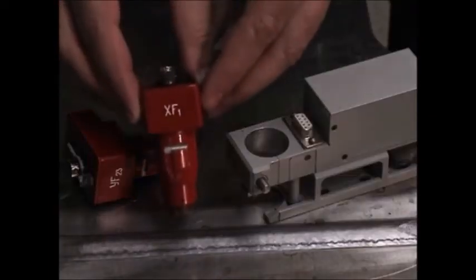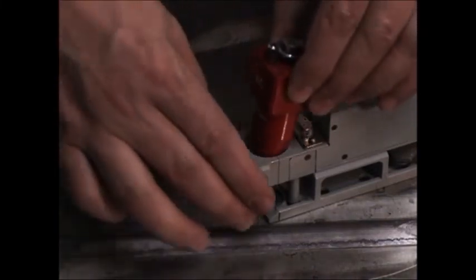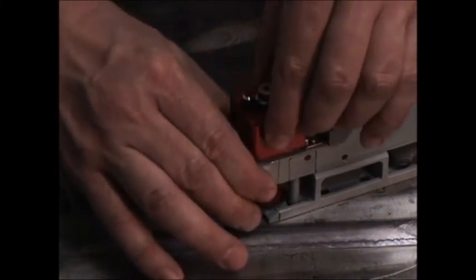The next step is installing the gauge to measure the velocity of longitudinal ultrasonic wave that is perpendicular to the material surface.